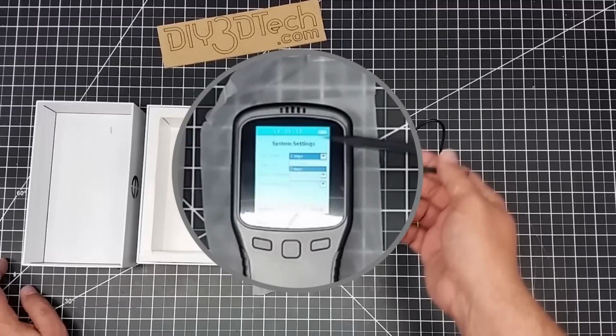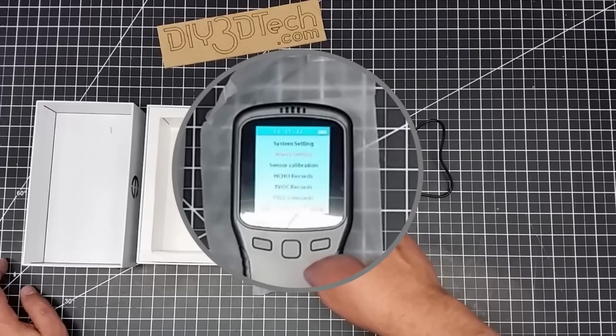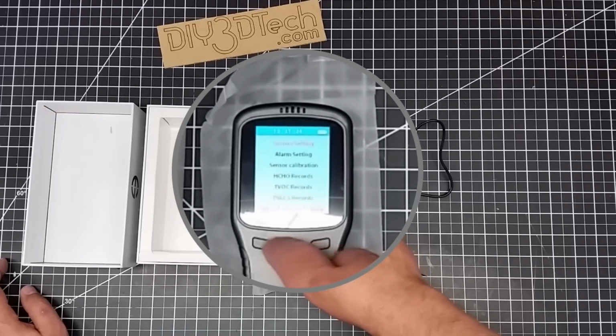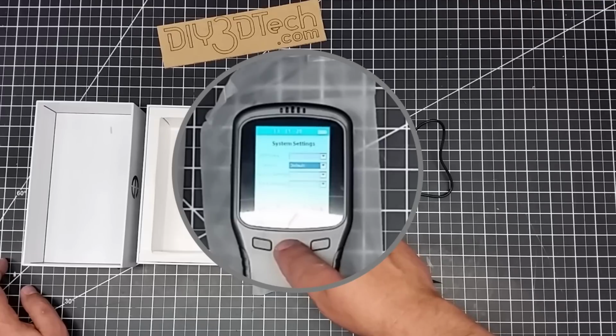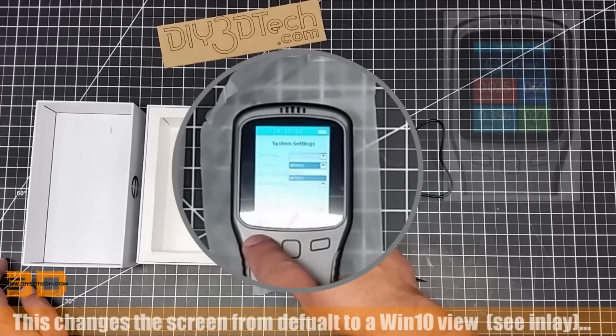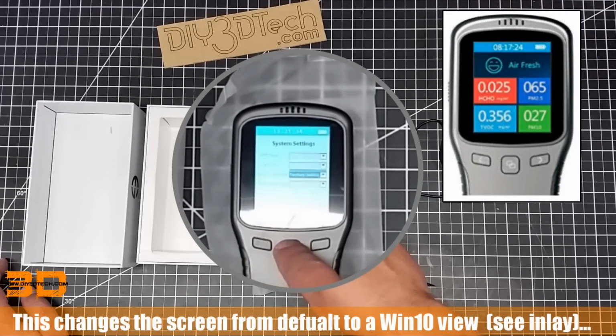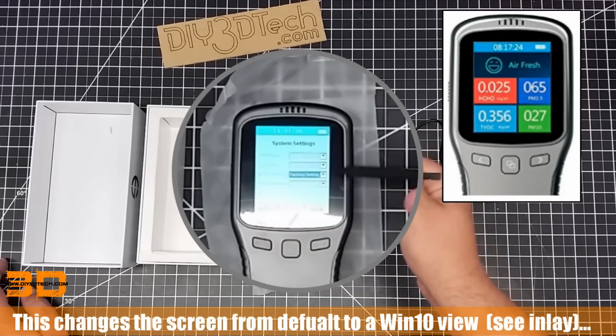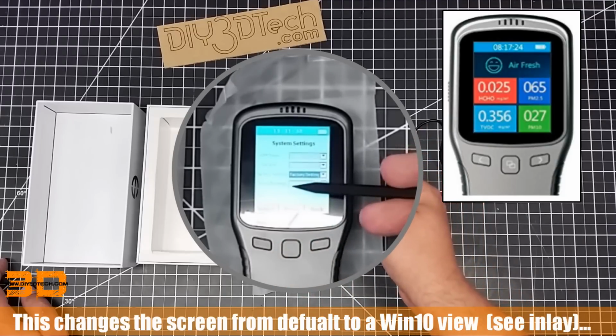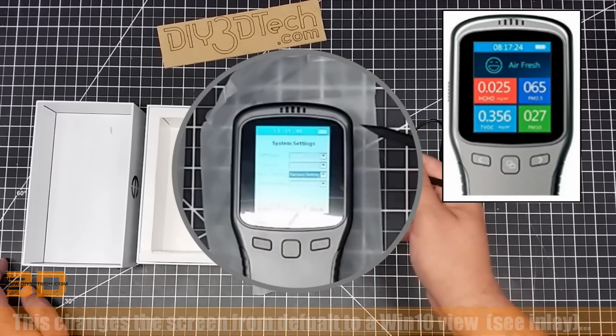So I've got it selected for 20 minutes. You can go up to 2 days, but you're obviously going to need to charge the battery. Oops, keep pushing the round button here. If we go back, again we can look at the version, so Win 10, and we leave it at default. You can do a factory reset here. We can also do time settings here to change the time.